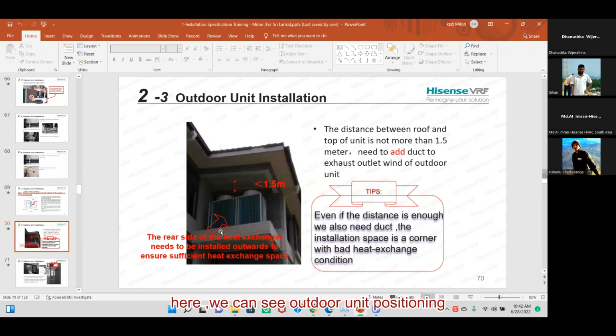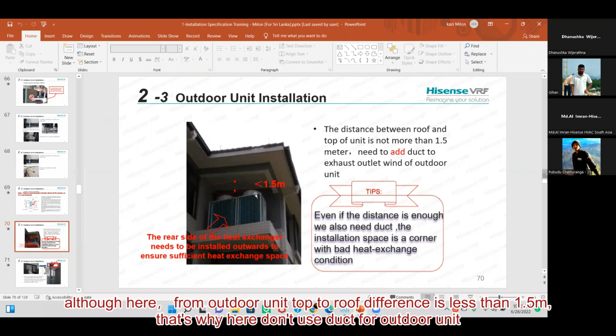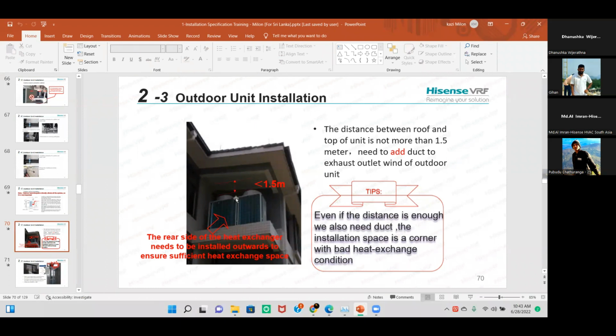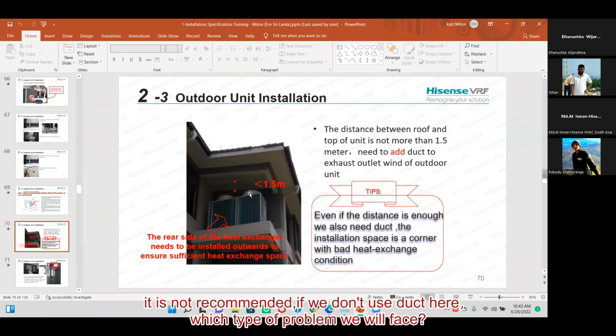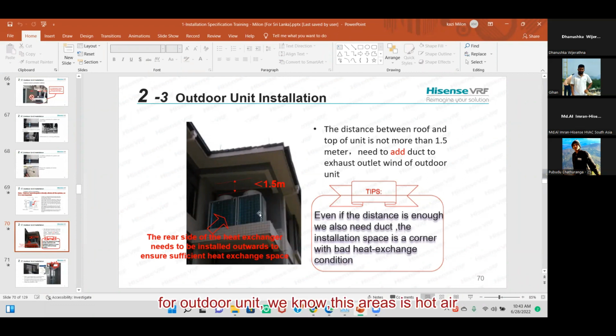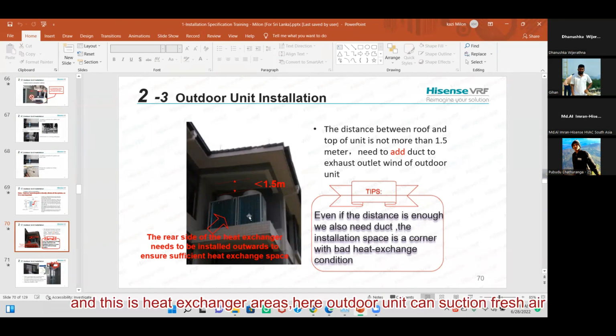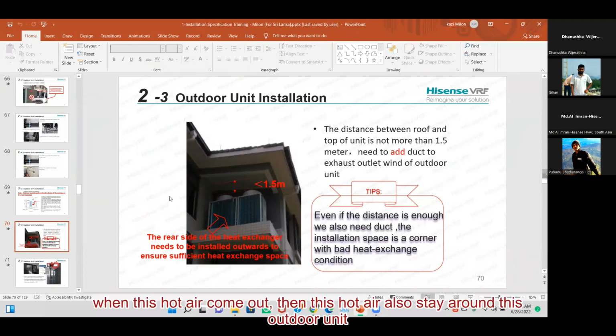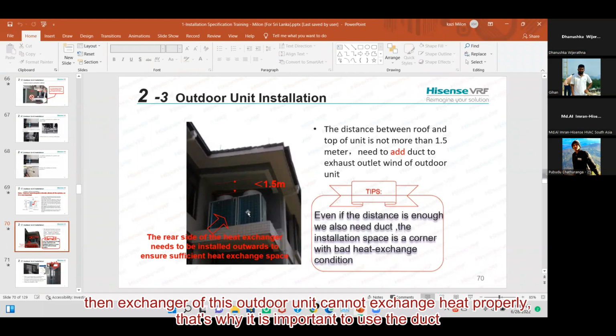Here we can see outdoor unit positioning. Although here the distance from outdoor unit top to roof is less than 1.5 meter, that's why here they don't use a duct for the outdoor unit. It is not recommended. If we don't use a duct here, which types of problem will we face? When the outdoor unit discharges air, we know discharge air is hot air, and the heat exchanger area of the outdoor unit sucks fresh air. When this hot air comes out, then this hot air is also sucked into this outdoor unit. Then the heat exchanger of this outdoor unit cannot exchange heat properly. That's why it is important to use a duct here.